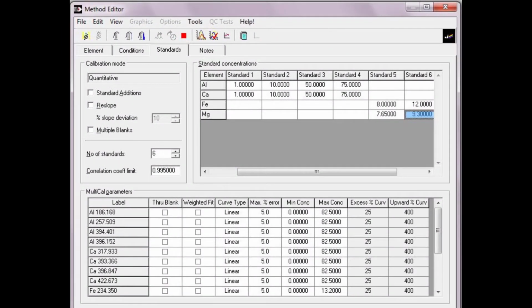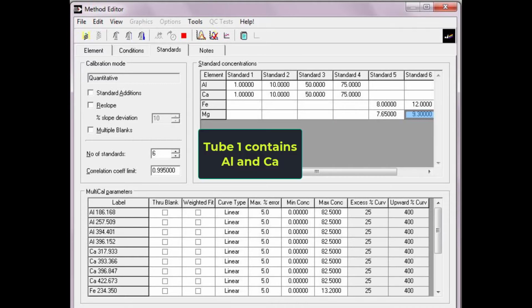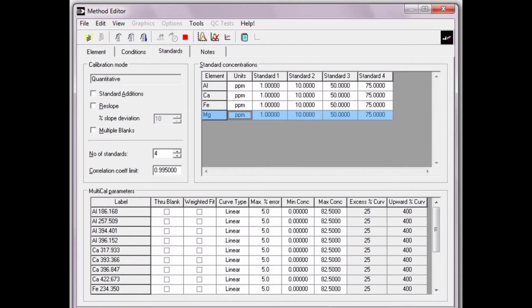Insert your calculated standard concentrations from lowest to highest, going from left to right. If you have more than one element prepared in a tube, you should list those values under the column for the same standard number. If a standard is missing from your centrifuge tube, just leave it blank. In this example, 4 elements have been selected, and each tube of standard contains all 4 elements of interest. Now press Ctrl S to save and X out of this window.